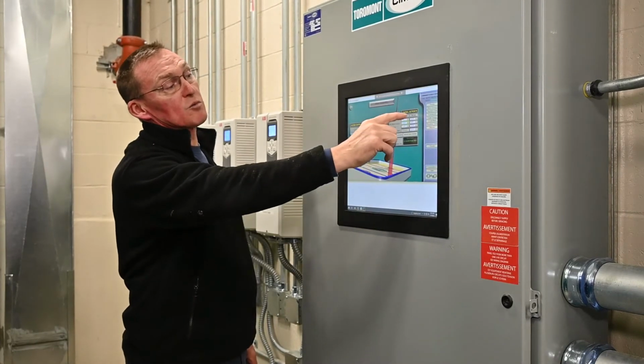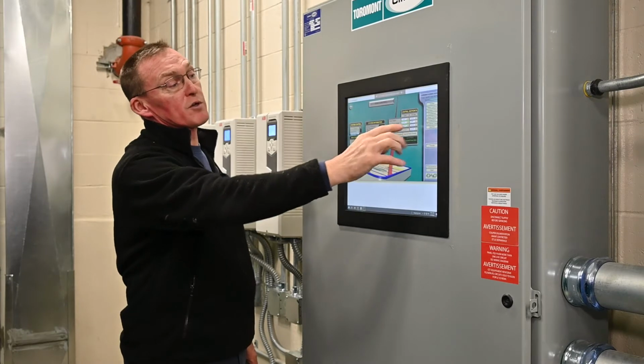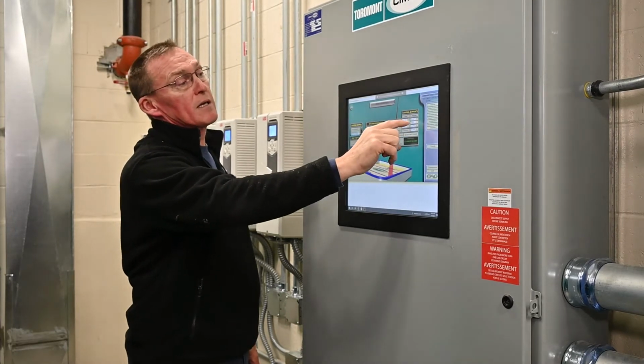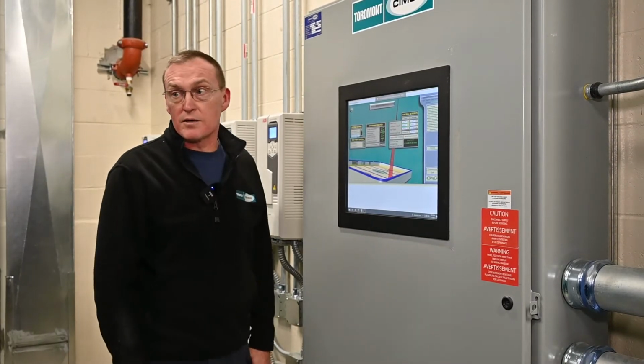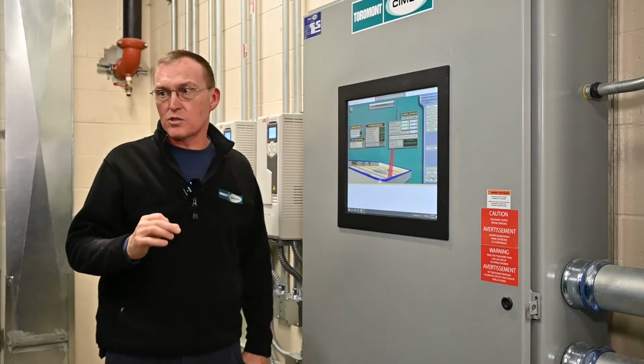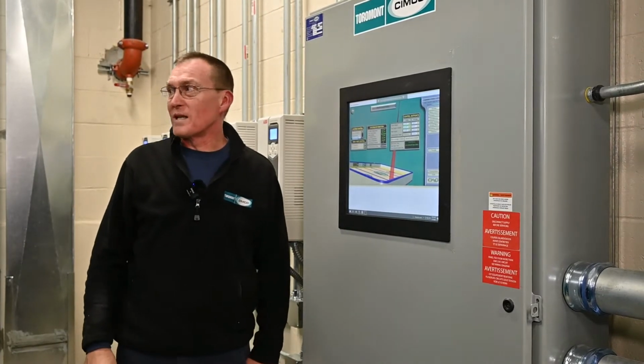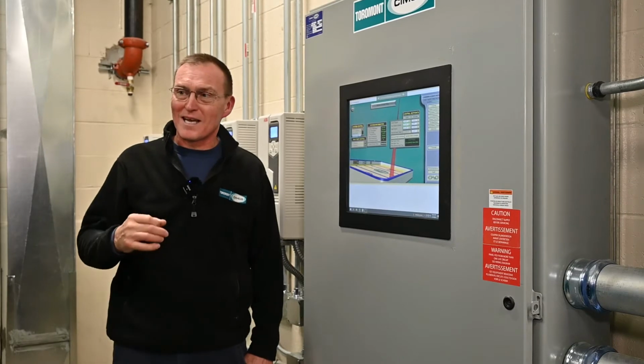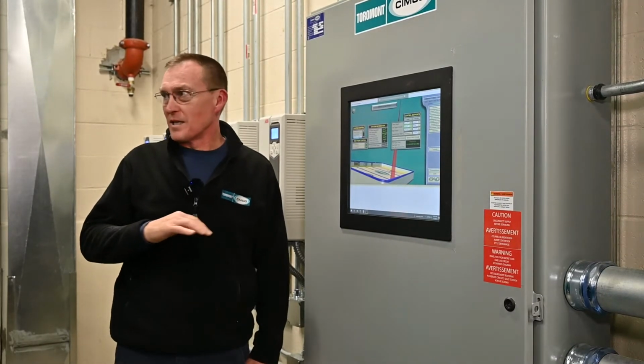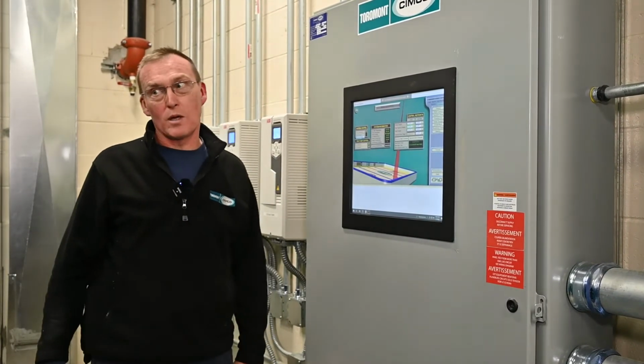Once you do that, it switches all your temperatures over to here. If you don't have anything programmed in night or day, it'll switch it right to day to 8 degrees. 8 degrees is the lowest you can go. The computer won't let you. Why? Because of the glycol freeze point. It won't, and trust me, that's some cold glycol going out there.